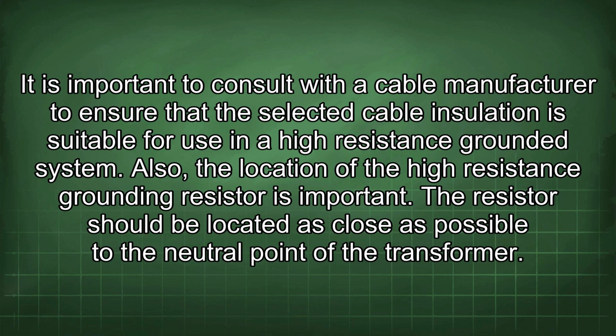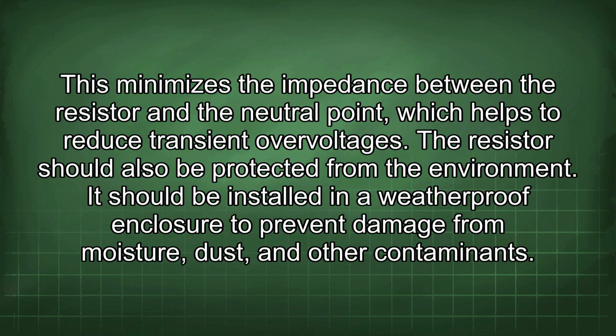Also, the location of the high-resistance grounding resistor is important. The resistor should be located as close as possible to the neutral point of the transformer. This minimizes the impedance between the resistor and the neutral point, which helps to reduce transient overvoltages. The resistor should also be protected from the environment. It should be installed in a weatherproof enclosure to prevent damage from moisture, dust, and other contaminants.